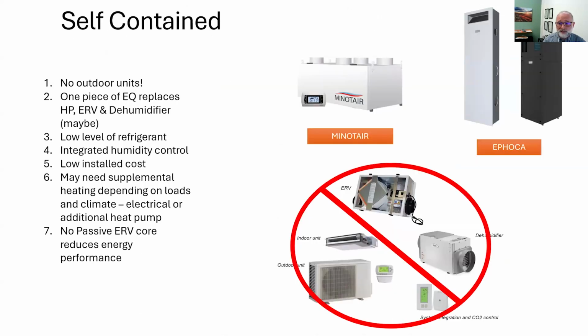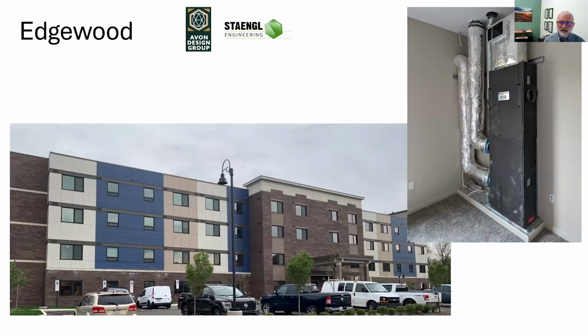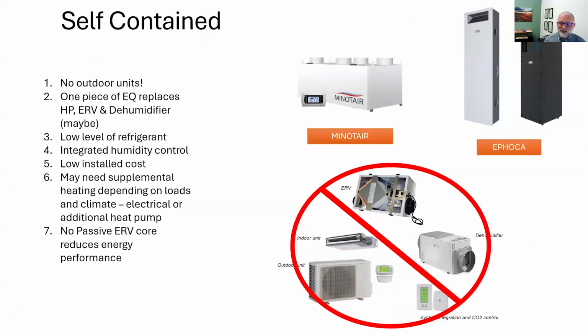A new approach, which is gaining popularity, is the use of all-in-one style pieces of HVAC equipment. There are several pieces of equipment on the market that combine heating, cooling, ventilation, and dehumidification in one device. The hope is that these units will drive down system cost and reduce on-site labor by reducing ductwork and equipment installation labor. Additionally, they address the refrigerant issues as all of the refrigerants are combined within one device, and there's no site-installed refrigerant piping running through the building.